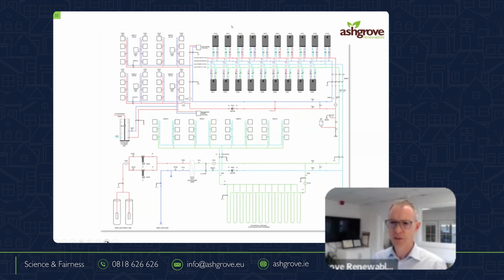The heat pumps are running at 500 kilowatts, just say. So I need to get 200 from here. In this case, I'm going to say 200 as well from ground loops. And in some instances, there might be a shortfall. In this case, we'll use open loop. But of course, we have heat exchangers, we have filtration and all the rest of it here.